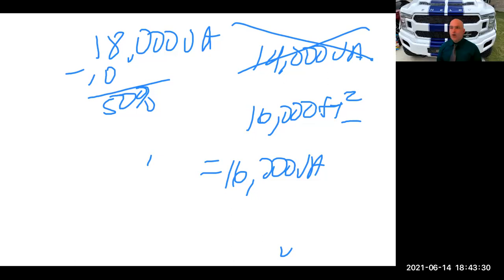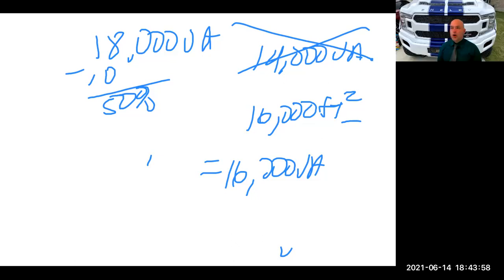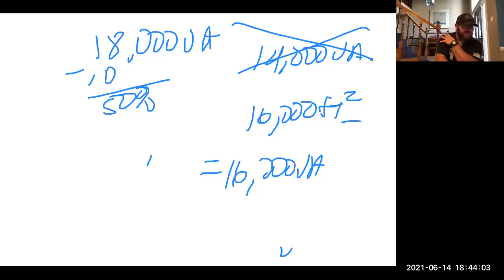And that matches if you go to 240.4(D). 240.4(D) also has those two conductor sizes listed, and you have the same fuse allowances with a 7 and 10 amp fuse respectively, given certain circumstances as well. It's not really a calculation though. It's more of a table reference. I don't want to presume that that's what you had, but that's a question that's come up recently as far as the ampacity of a 16. And like I said, I may be confusing it with the code section.